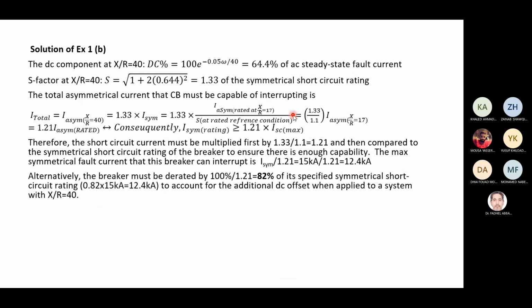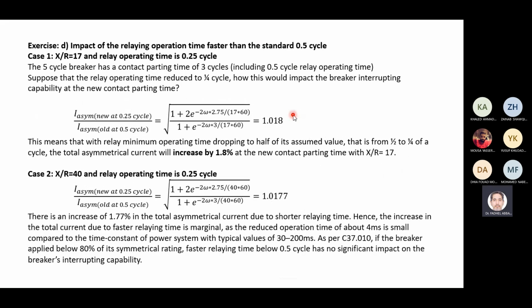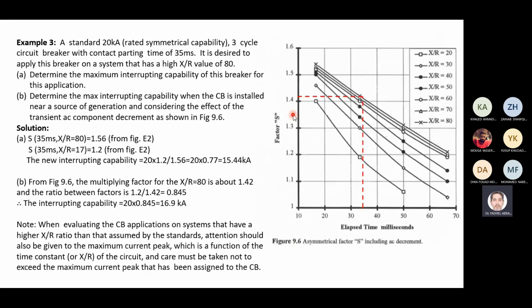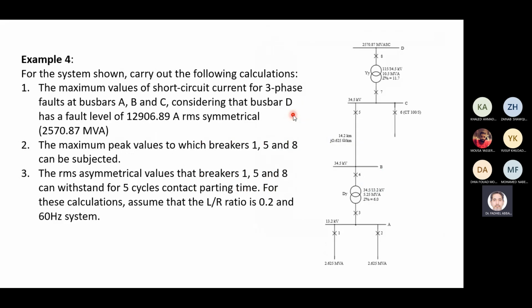اوكي شباب، so these are examples. We have many examples I prepared here. You can refer to it. بس في كل الأحوال إحنا لازم نعرف شنو من السيستم. I already علمتكم من قبل إن we need to find first short circuit current اللي هو 3 phase short circuit current at each breaker, right?